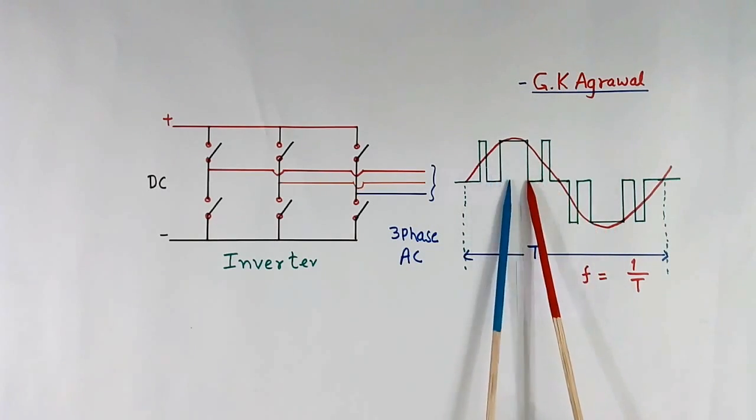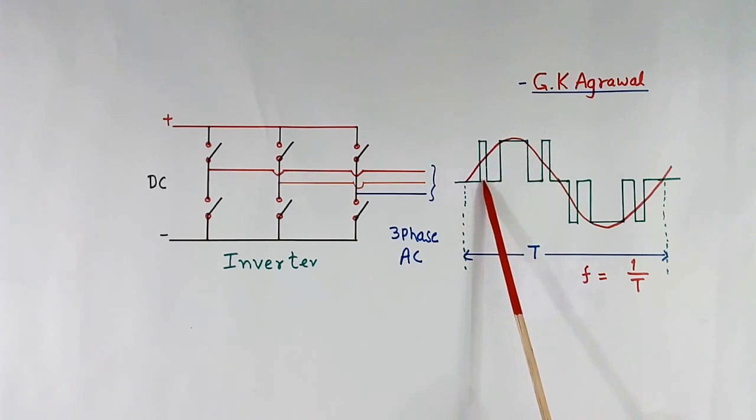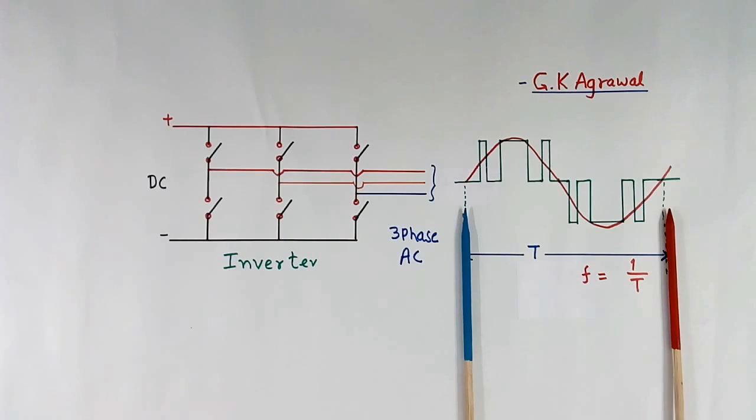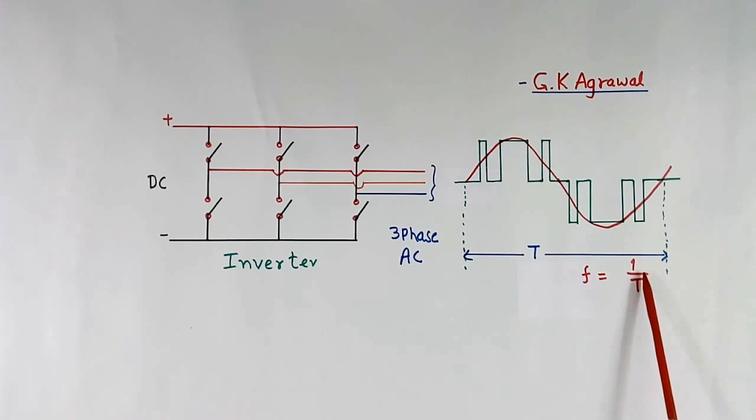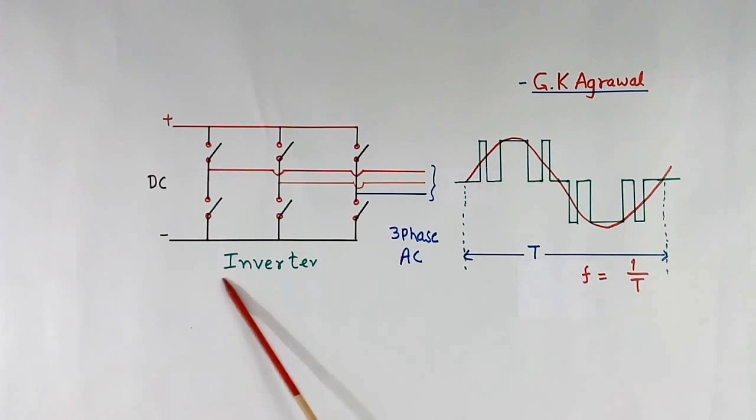See here. IGBTs are on for longer duration, so we get more voltage. Here on period is less, so we get less voltage. So this is AC. I have shown only 1 phase. There will be 3 phases like this. And this is the time period of this red color AC. And frequency will be equal to 1 by T. If we want motor speed more, we want frequency more. So T we have to reduce. So this will have to be reduced. So this inverter does 2 functions mainly. One is to generate 3-phase AC, and second is to control the frequency.